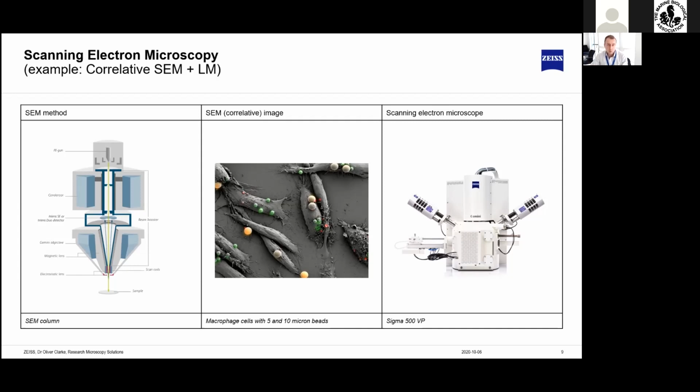And I talked about microbeads for imaging, and what you can actually see in the middle there is right in front of your eyes these micron beads. So they're 5 and 10 micron polystyrene beads with a fluorescent compound inside them. And they're used to calculate these point spread functions in microscopes like confocal microscopes to check that the optics are orientated.